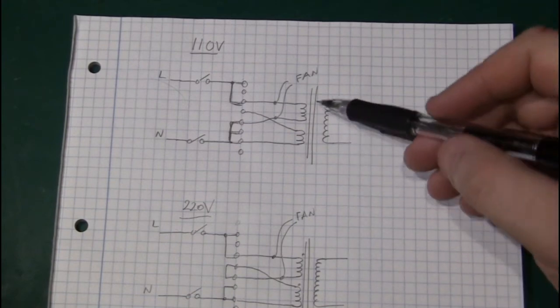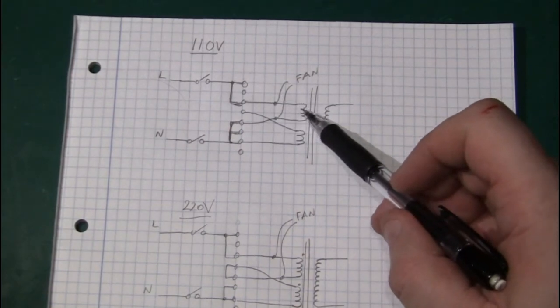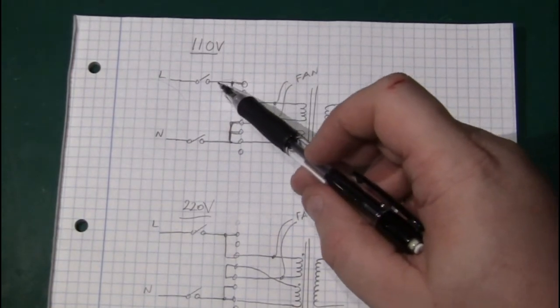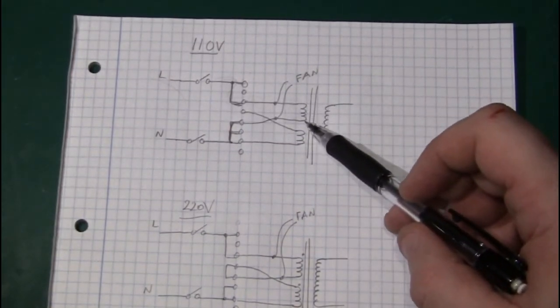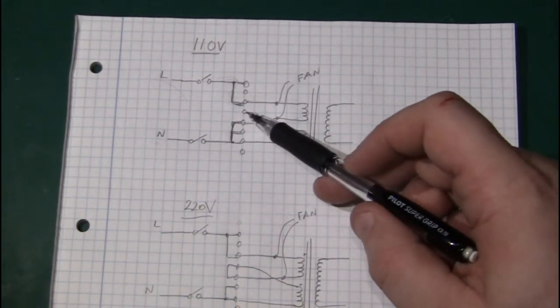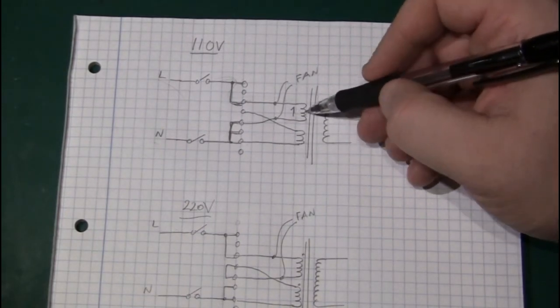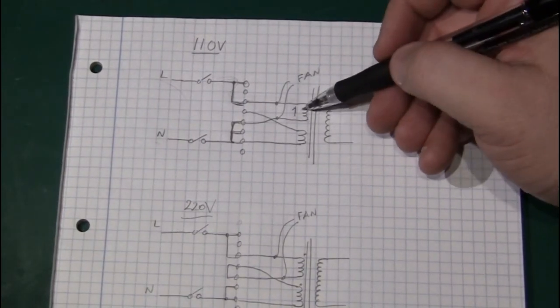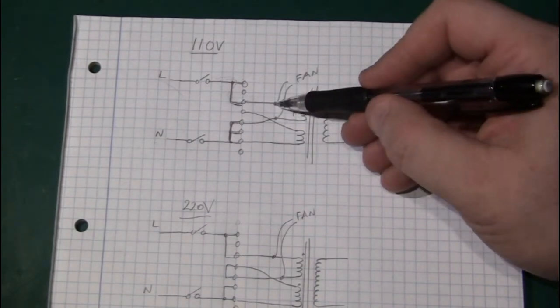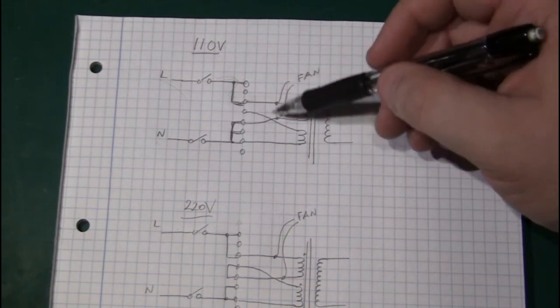And what happens then is that the transformer, which has two windings, is connected through here from live. The current flows in here through the transformer winding and back out again. And the other transformer winding is not connected. So it's just using one winding here. So we have 110 volts across one single winding here. And as you can see, the fan is connected between these two wires. So everything is good. The fan has 110 volts.